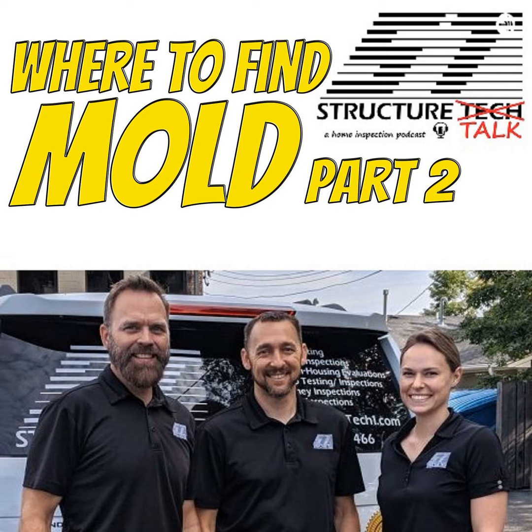That air exchanger is pulling in so much air, and people running them in summer are pulling dust, humidity, and mold spores right into their air exchanger. Most of them are made with flex duct that's insulated, and I believe it's really hard to clean flex duct. So I open up the air exchanger, put my hand into that intake duct, swab it, and I know that almost every single one is full of mold. So I've actually been thinking about proposing a code change, because some people have a really nice situation. If your air exchanger is in a utility room and your intake duct is about 4 or 5 feet long, just replace it every 3 or 4 years because it is going to grow mold.